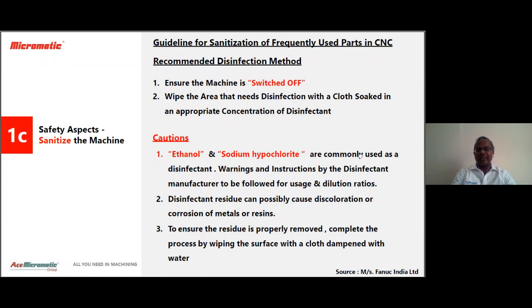Before sanitizing, the machine should be switched off. After ensuring the machine is switched off, the full machine has to be thoroughly wiped with a cloth soaked in an appropriate concentration of disinfectant solution. The disinfectant solutions commonly used are ethanol and sodium hypochlorite. These are the two solutions commonly used as disinfectants. There are a few cautions and warnings to be taken care of while using these solutions, because the ratio to be mixed with water has to be as recommended by the manufacturer of the disinfectant solution. So you have to take care while mixing the ratios.